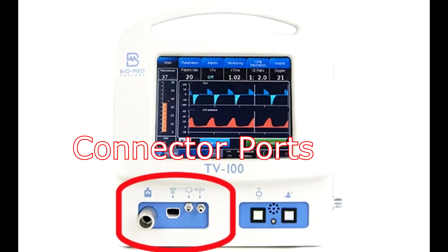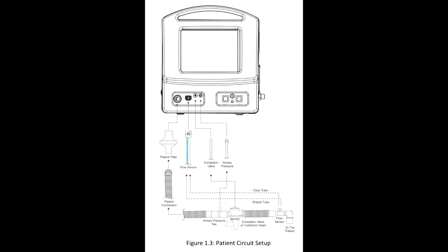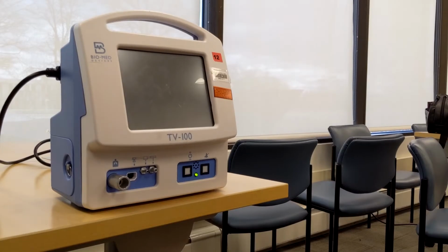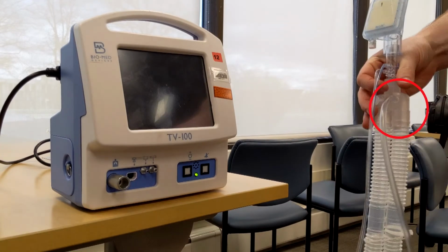To properly attach your circuit to the ventilator, place the tubing to its appropriate connector. The order to this does not matter, just that it is placed tightly and to the right connector. Each tubing has its own size and won't allow you to place a tubing on the wrong connector. For our purpose today, we are going to start from the middle and work our way outward. Grab the airway pressure line located on the expiratory limb just before the Y piece.